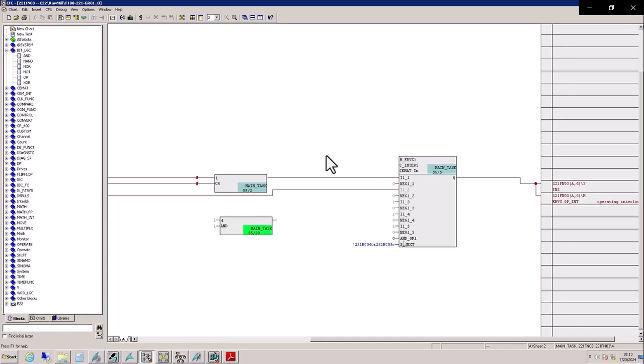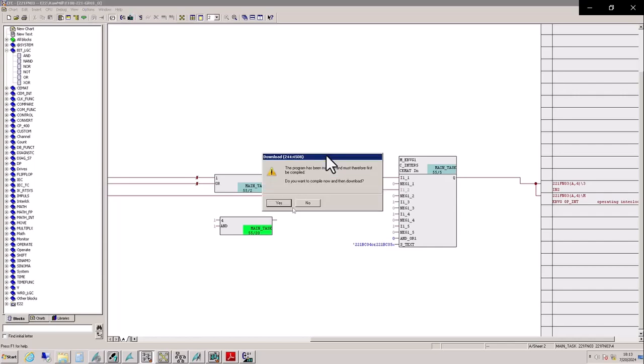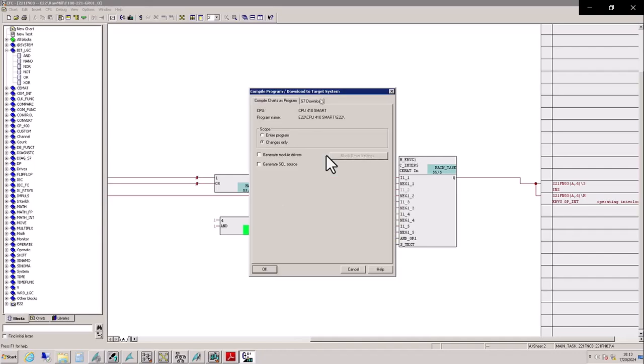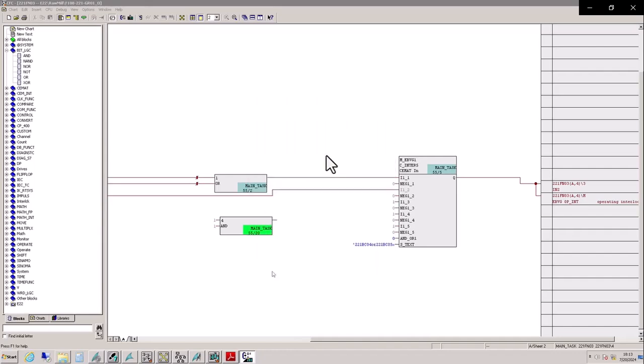Well, in order to remove the bypass, you can simply reconnect the 221BF03 signal to the interlock block, and you will perform the compilation and PLC program download as I did before. And this is how you will restore the interlocking signal 221BF03 into the operation interlock of the 221FN03 fan. Again, it will take some time while it compiles and downloads the program to the PLC.